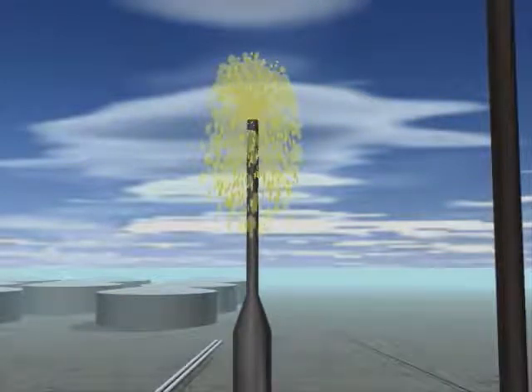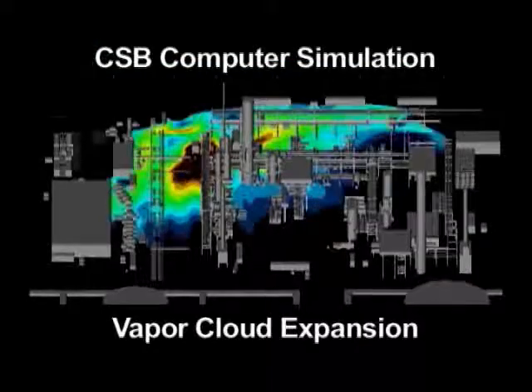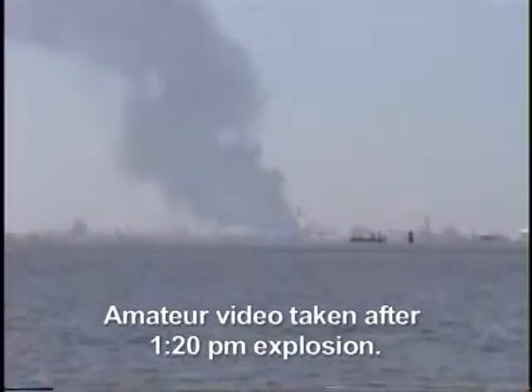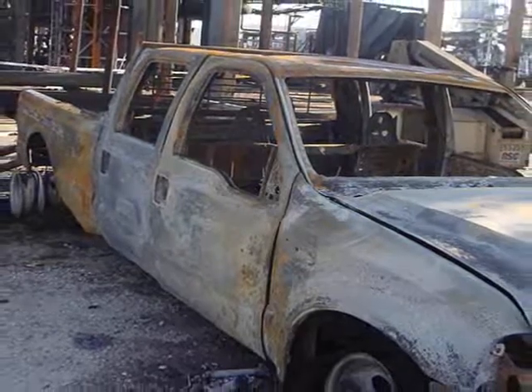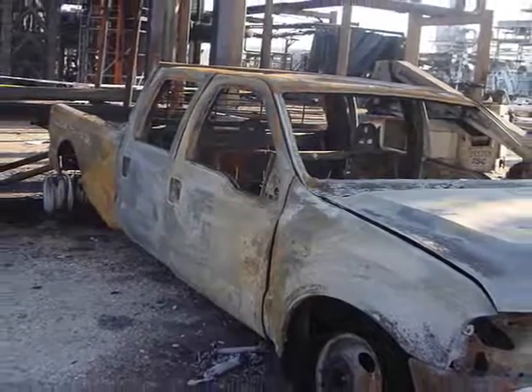Liquid fell to the ground, creating a large, flammable vapor cloud. This model predicts how far the vapor cloud expanded across the area just 1 minute after the release began from the stack. At 1:20 p.m., the cloud ignited, causing a series of explosions. The CSB believes the vapor cloud was most likely ignited by a diesel pickup truck parked about 25 feet from the blowdown drum.